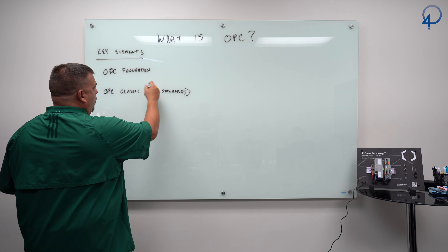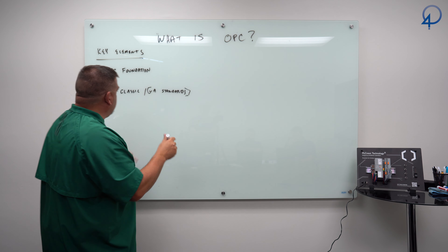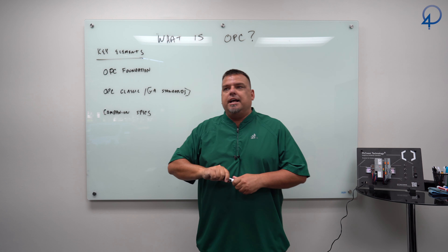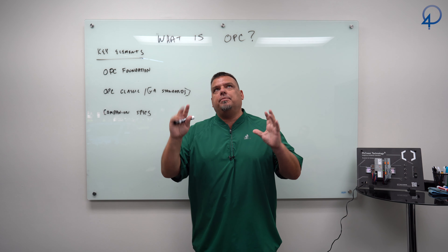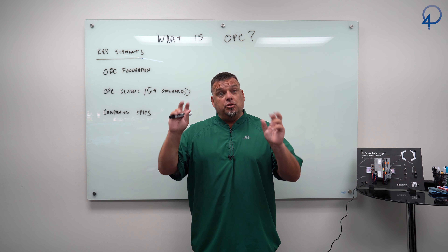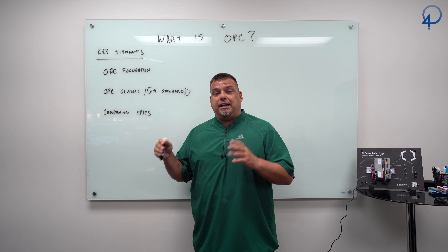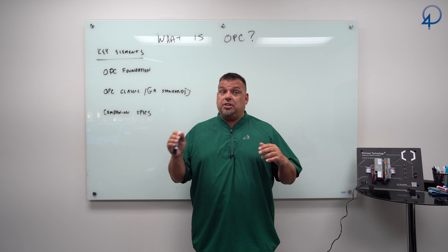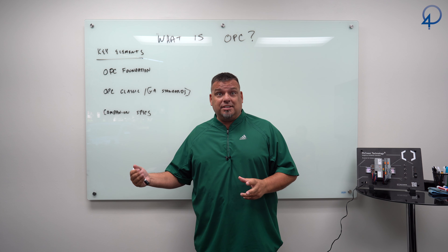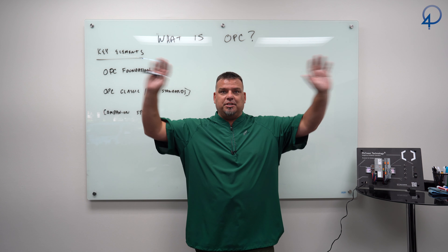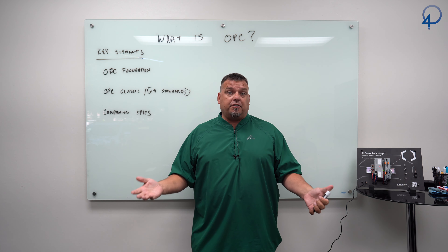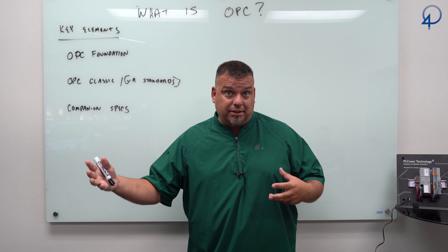The third piece is companion specs. Companion specifications are offshoots of the base standard that tell you how to organize data. The best way to define most companion specs is: it's a specification that tells you how to create a user-defined data type for a specific type of equipment. In OPC they call these information models, but they should really be called data models — hierarchical data models. The companion specs create those models. A CNC machine or a lathe would be a good example.